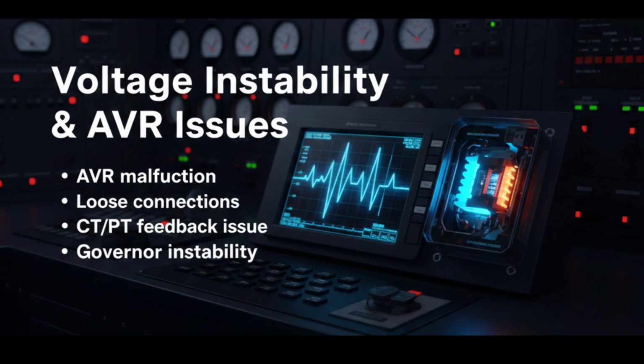Voltage instability or AVR issues. Voltage instability can damage sensitive equipment like navigation systems and automation panels. If busbar voltage is fluctuating, check the AVR first. AVR controls excitation of generator. If malfunctioning, voltage will not remain stable. Check excitation voltage. Inspect terminal connections for looseness. Check CT and PT feedback signals. Sometimes governor instability can also indirectly affect voltage. Observe voltage waveform and meter readings carefully. Stable voltage is essential for proper operation of electronic systems on board. Small fluctuations can become big problems if ignored.